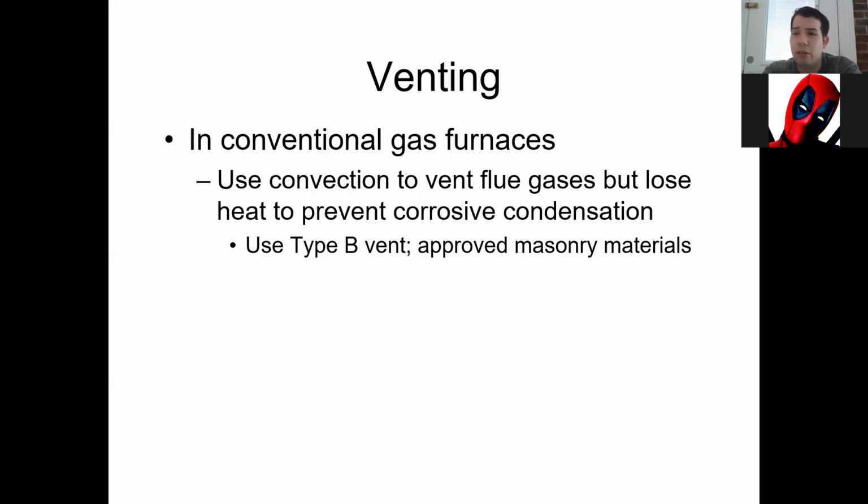So usually the masonry is sized too large, so the flue gases can condense very easily on the walls inside, and they will literally eat away at the brick and mortar. And I've seen videos of houses where it's been such a big problem that the whole chimney just collapses off the side of the house, just because flue gases went out, cooled off, and ate through everything.